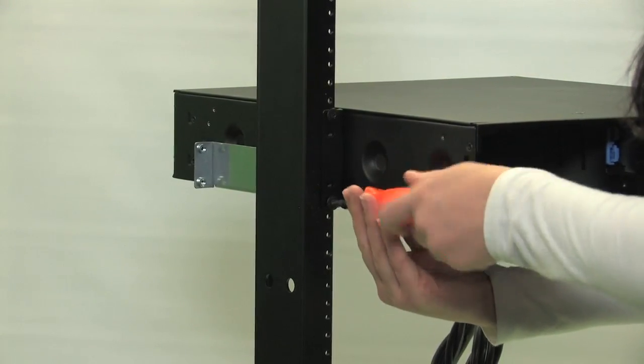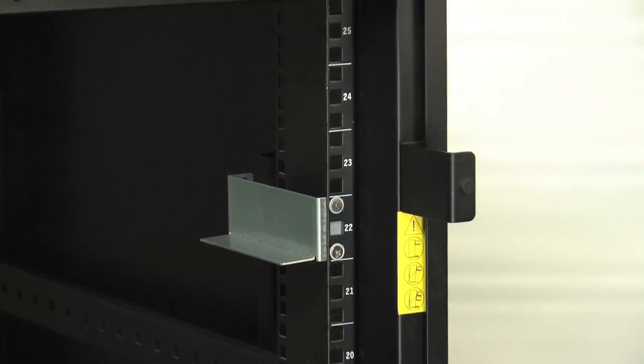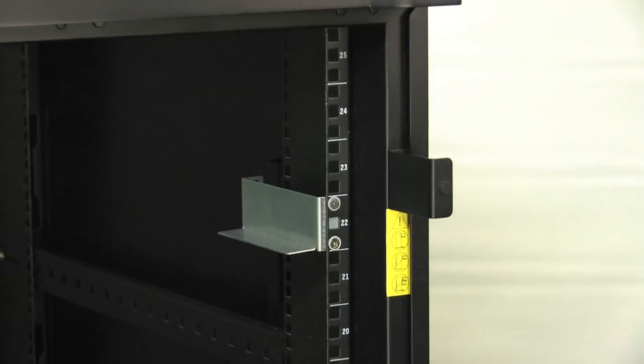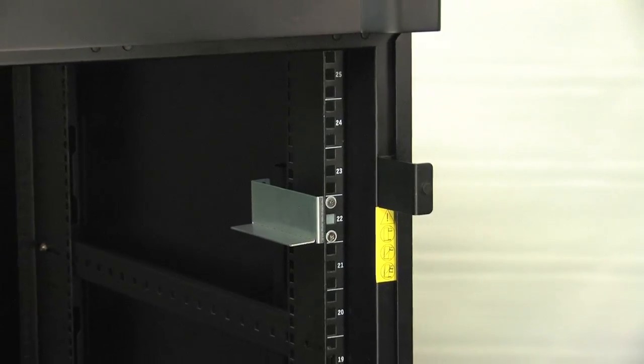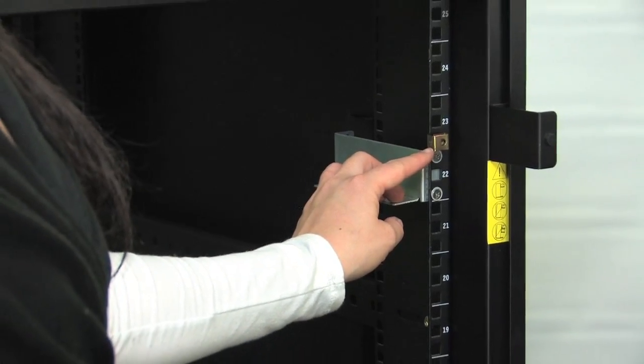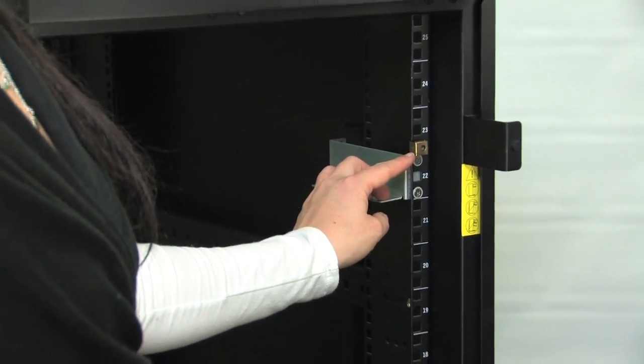As mentioned previously, these brackets can also be used for a four-post installation. Take the flathead screws provided and screw into the U position to the front backside of the front rail of the four-post rack. Snap the cage nut in one U position above the bracket.